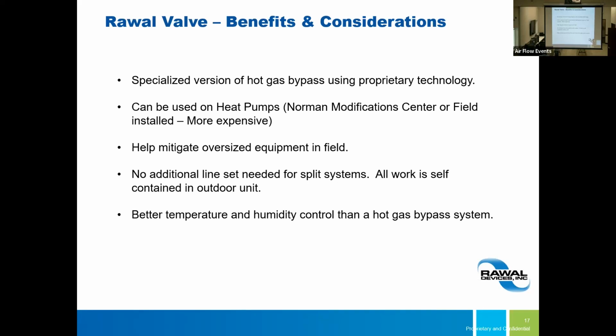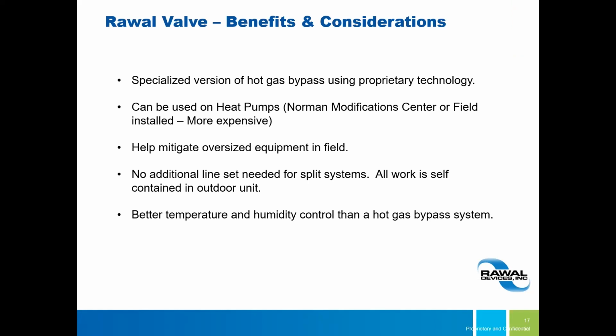I got it. So this is a strategy where there are actually energy savings benefits when you're thinking about unloading the compressor with a Rawal valve. And obviously you do get dehumidification as well. It's not a different version of hot gas reheat, but it's a lot better than hot gas bypass. So let's go to the next slide.